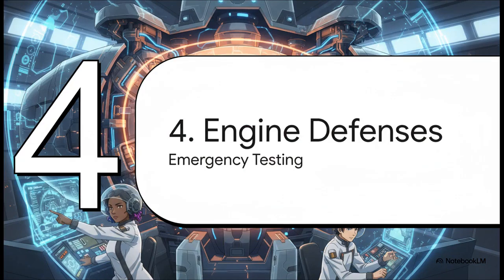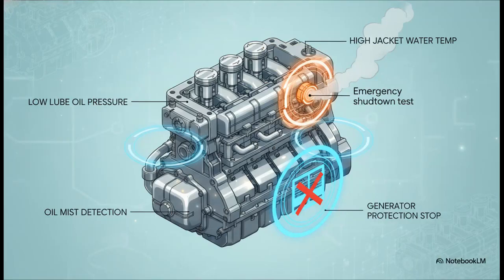Section 4. Engine Protections and Emergency Testing. Let's dive deep into our test plan for the engine's emergency protections. We meticulously check the engine control system alarms. This includes methods to verify oil leak protections, crankcase differential pressure, and of course, a detailed plan for testing the emergency shutdown if an engine overheats. If you ignore these checks in TAM, you risk collapsing the entire connected power grid.